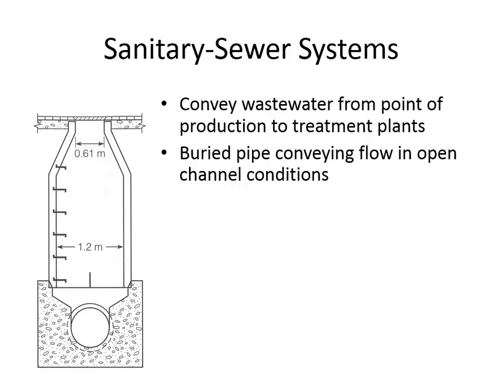The pipes are buried, and the main objective in a sanitary sewer is to convey the water without having to pressurize the pipe, so it's an open channel in spite of the fact that it's a pipe. So far in this course we've had two distinct things: pressurized pipe flow (closed conduit flow), and open channel flow in trapezoidal or rectangular channels. Here, the sewage is conveyed through a pipe but it's not pressurized, so the pipe has to be going downhill to convey the flow.